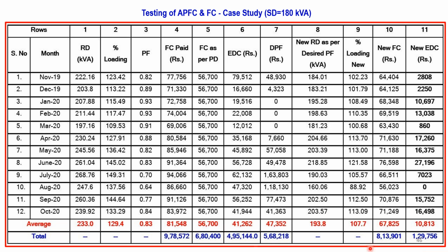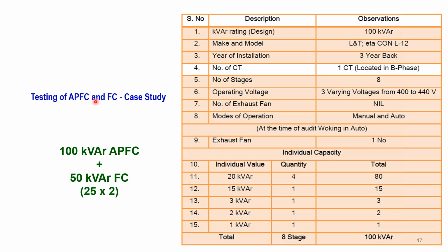Now what is the reason for not maintaining the power factor? This company has an APFC, and along with the APFC they have a 50 kVAr fixed capacitor also. Now this is the design, the specification of the capacitors. The 100 kVAr capacitor is a single CT configuration, so it is located in the B phase itself. Now it's an 8-stage configuration. Now all the stages are represented here. Apart from that, they have 25 kVAr, 2 numbers of fixed capacitors.